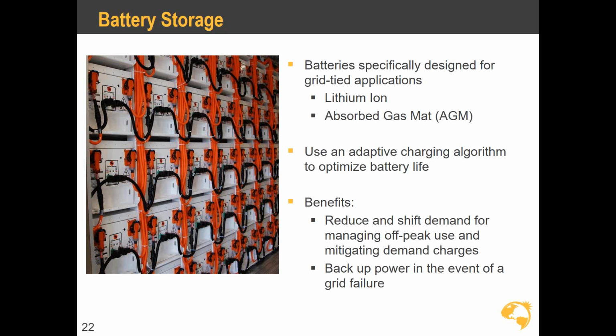But let's say your battery was a utility battery that a power company was going to be cycling on and off during the day to help level the load on the grid, or a battery in a commercial setting being used to mitigate demand charges - turned on at the same time as large machinery to help mitigate some of those power draws. If it was going to be cycled heavily, in that case we'd go with lithium-ion batteries. They have a much higher cycle life, lower maintenance, but they do have an added cost.